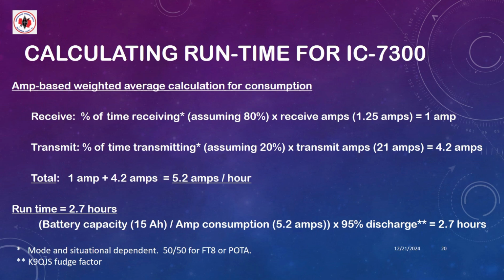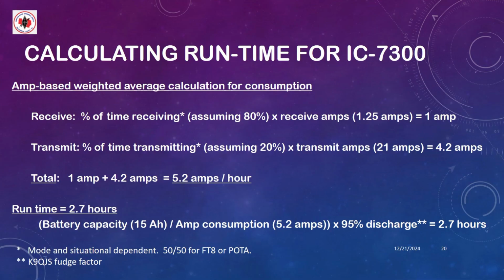So operating off a battery only, the runtime would be 2.7 hours. The battery capacity, 15 amp hours, divided by consumption, 5.2 amps, times 95% discharge. That's a bit of a fudge factor, but if you remember the discharge curve from the previous slide that I showed, the battery cuts off after about 95% being discharged. So 2.7 hours is the runtime, average runtime.